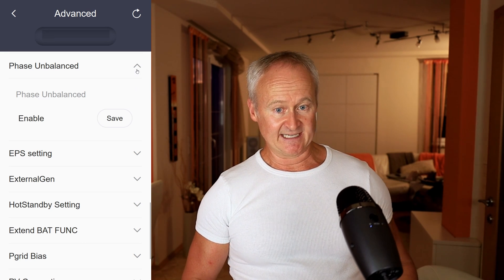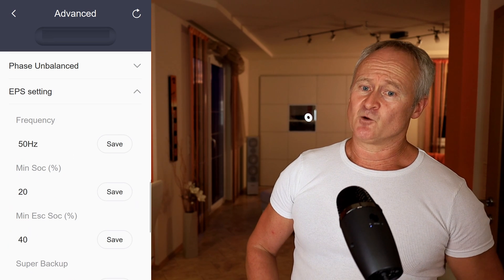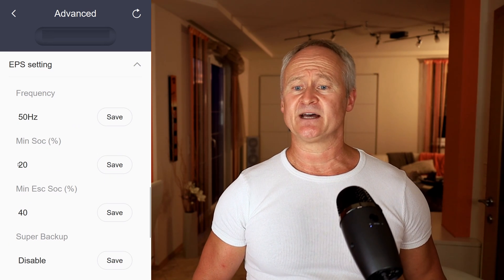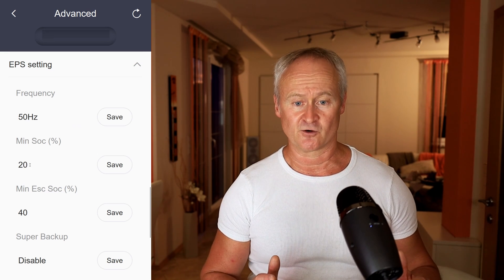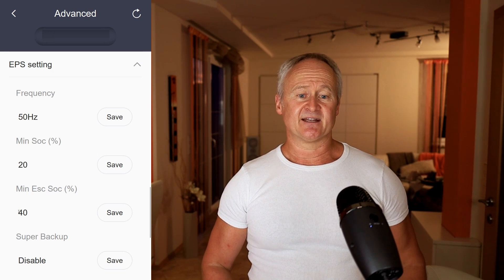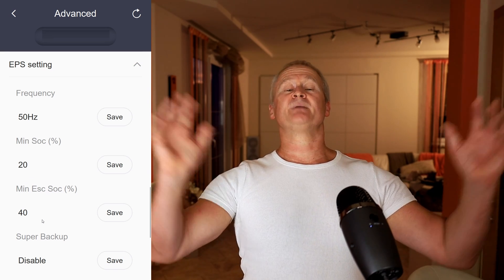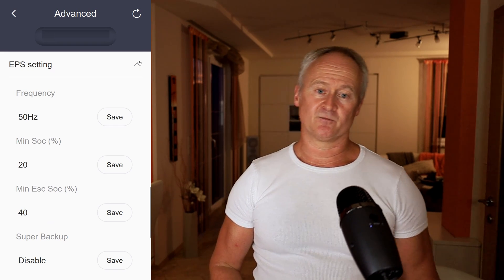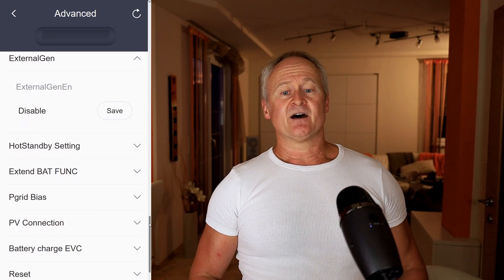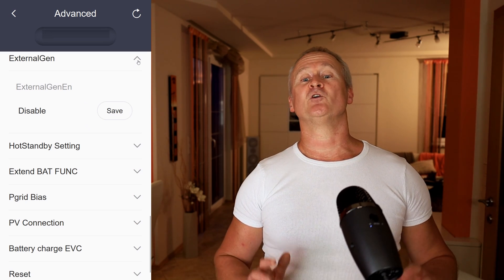I will cover the Phase Unbalanced topic in more detail in a separate video. In the EPS settings, you define the frequency at which the inverter should output power in EPS mode. Additionally, you set the minimum state of charge of your battery at which the EPS output should stop supplying power — below that threshold the EPS output will be disabled. You also set the SOC level at which the EPS output should be reactivated after being recharged by the sun. External Generator is a topic for which I made a very long video on my German YouTube channel. I will also do it in English. In regular operation, this function is disabled — it involves integrating a power generator into the photovoltaic system.